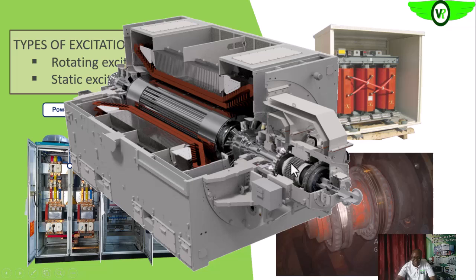So this is the slip ring arrangement that carries the power into the main field. This is the main armature. Are we getting it? So from the output of the main armature, we feed the excitation transformer. The excitation transformer will feed the static excitation system, and in some cases you have the thyristor rectifier. As you vary the rate at which the thyristors are fired, or the rate at which signals are sent to the gate of the thyristors, that will vary the firing rate and help to control the voltage that is coming out. So the output voltage will now be sent to the main field via this slip ring. Are we getting it?